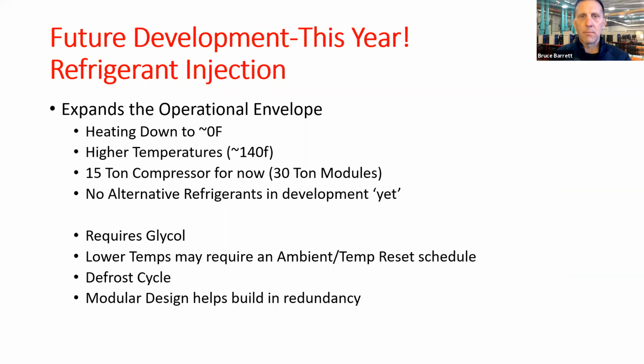All right, future development. This is where I believe things are going to really take off because of the limitations of the current compressor technology being about 40 ambient. Now, we can make hot water below 40 ambient, but it often needs a reset schedule to reset your hot water temperature. People don't like that very much.